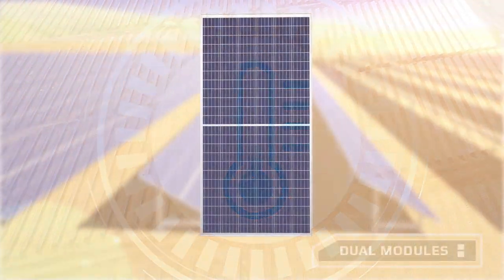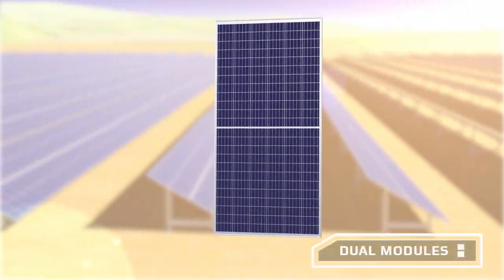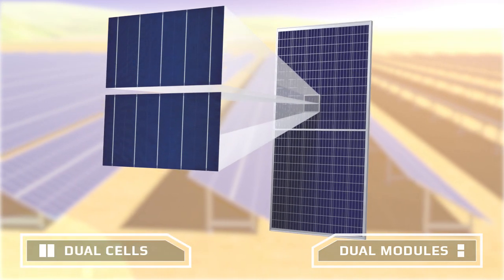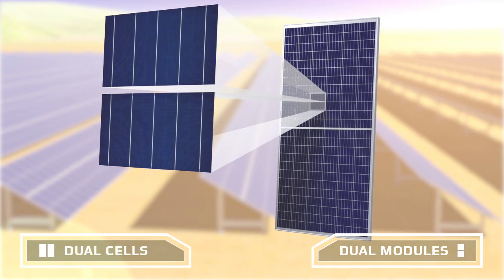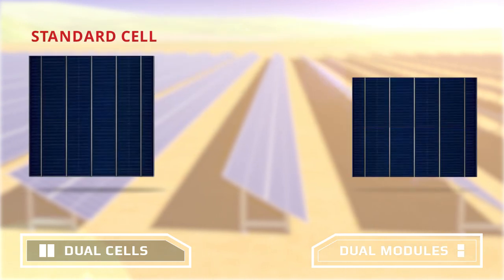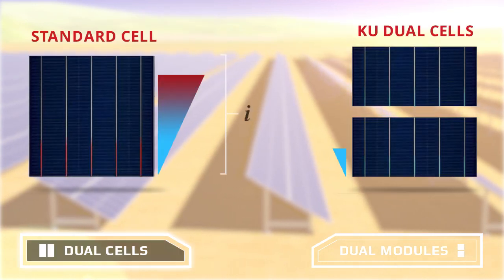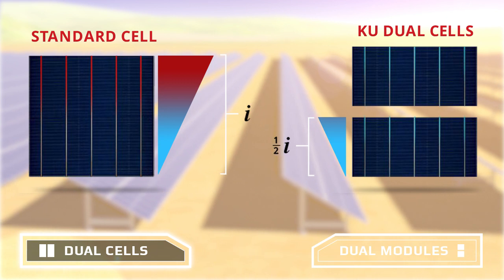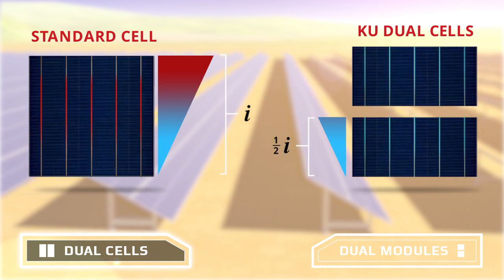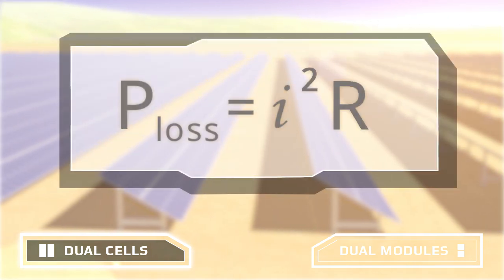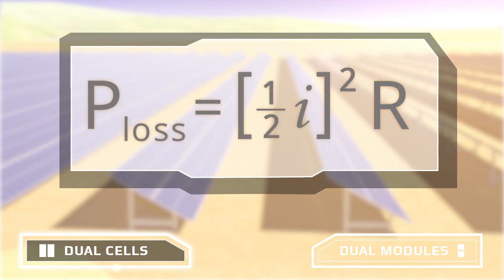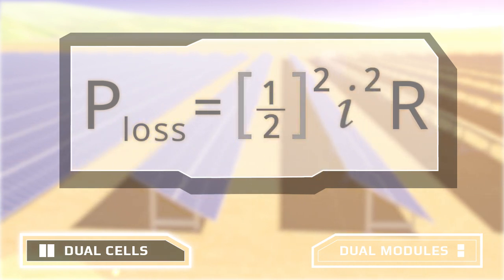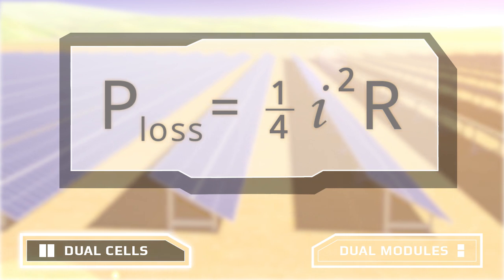The main differences between Ku modules and standard PV modules are dual cells and dual module design. Dual cells are half the width of standard cells. Cells with half the width generate half the current. Because the power loss goes as the square of the current, dual cells generate only one quarter of the power loss.